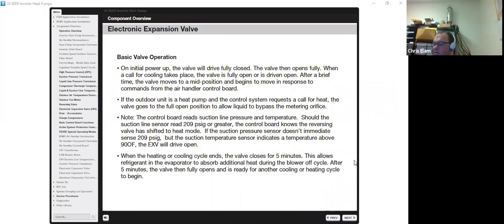With basic valve operation, upon power up, the valve will drive fully closed. Then the valve fully opens. When a call for cooling takes place, this valve is fully open or in the driven open position. After a brief time, the valve moves to a mid position and begins to move in response to the commands from the air handler. If the outdoor unit is a heat pump and the control system requests a call for heat, the valve goes to a fully open position to allow liquid to bypass the metering device. If you go into the EcoNet, you'll see a 496 valve position, which is typical. That means it's completely open and bypassing.